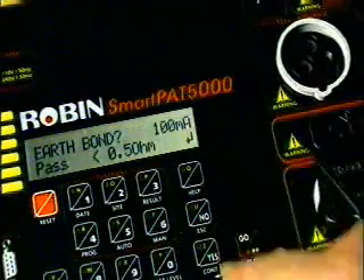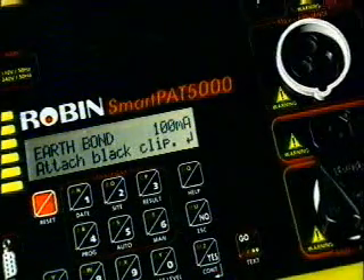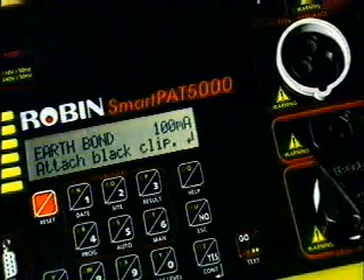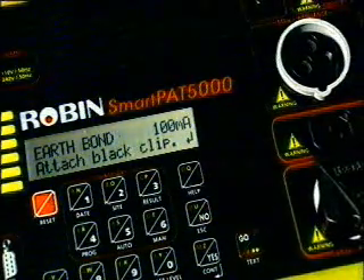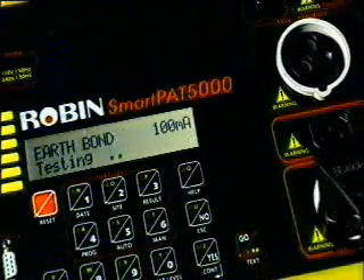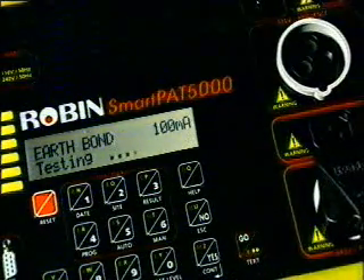When testing IT equipment, you must find a suitable exposed earth point to connect the earth clip. The earth bond test is carried out at a reduced current of 100 milliamps instead of 25 amps or 8 amps, to prevent sensitive electronic devices being damaged.